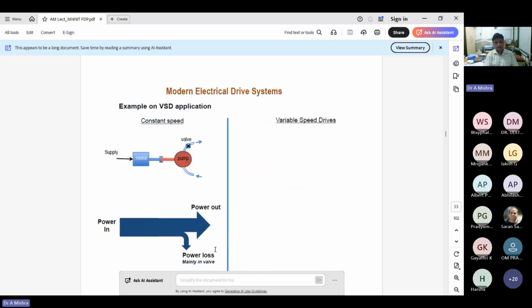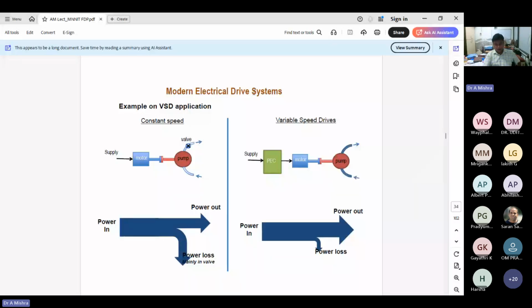One example we will see here, and we'll discuss the losses: if you have a pump, water flow is required and the motor is being supplied with power. If you want a lower water output in the conventional system, you close the valve to 20 or 30%. You get the rest of the water output, and the rest of the water will be blocked by this valve. But if you are using a power electronic system for the same motor and the same pumping application, then even when your water output level is lower, your losses will be less, because the motor speed will be controlled so that it operates the pump at a speed that provides only a certain amount of water.